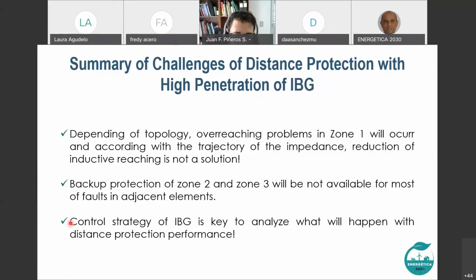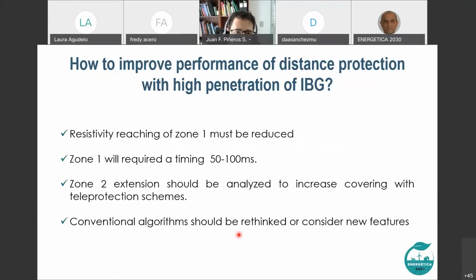And of course, as I told you, the control strategy of inverter-based generation is really a key point to analyze what will happen with the distance protection performance. And here the message is we really need a detailed model of the inverter-based generation if we want to be sure to see well the problems or the good performance of the distance protection relays in general. But of course, it's not applying only to distance protections. It's applying in general. If you put a line differential protection or directional overcurrent, the same applies.